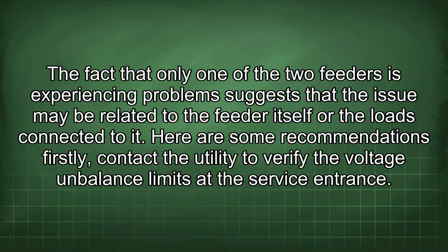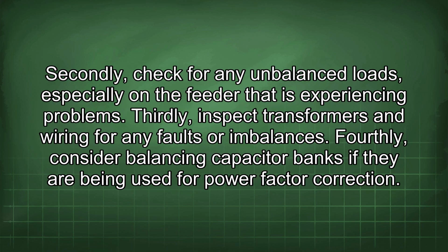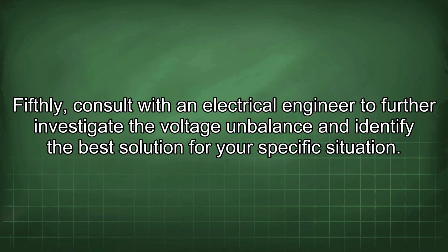Here are some recommendations. Firstly, contact the utility to verify the voltage imbalance limits at the service entrance. Secondly, check for any unbalanced loads, especially on the feeder that is experiencing problems. Thirdly, inspect transformers and wiring for any faults or imbalances. Fourthly, consider balancing capacitor banks if they are being used for power factor correction. Fifthly, consult with an electrical engineer to further investigate the voltage imbalance and identify the best solution for your specific situation.